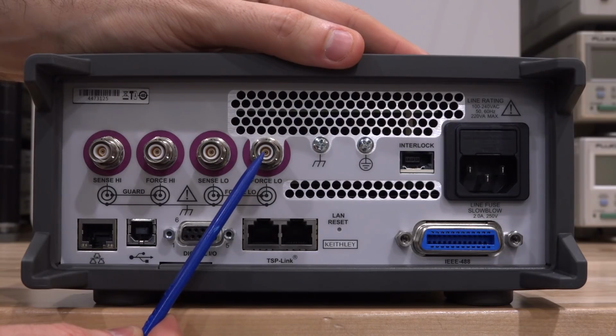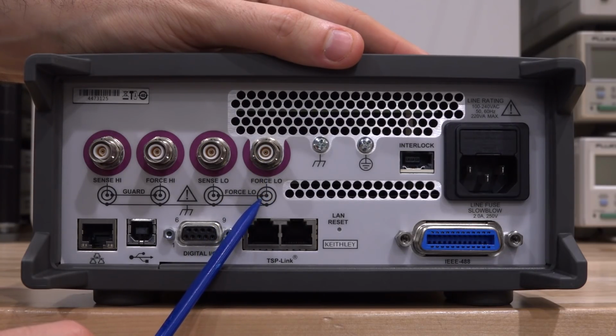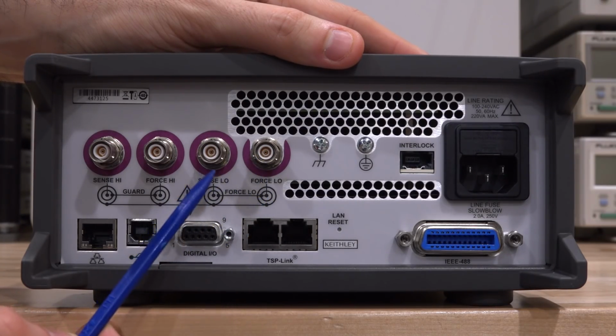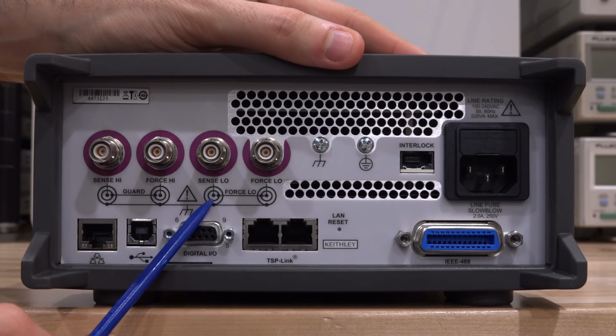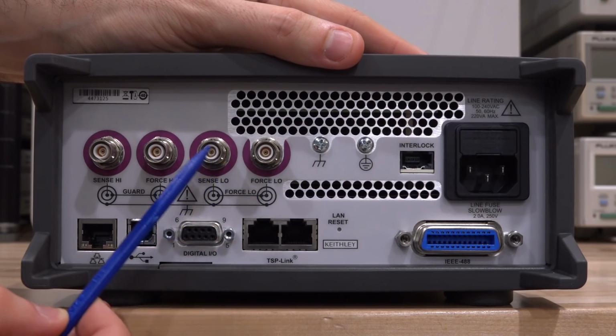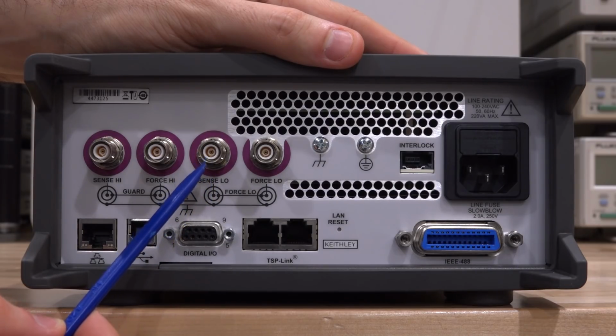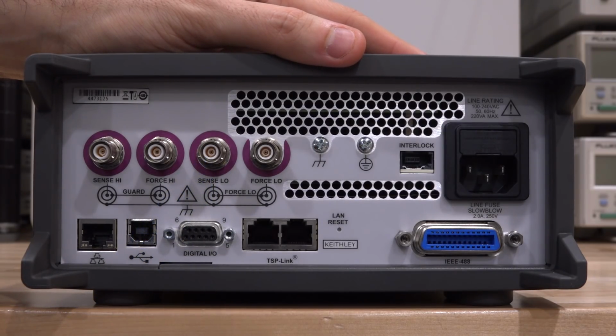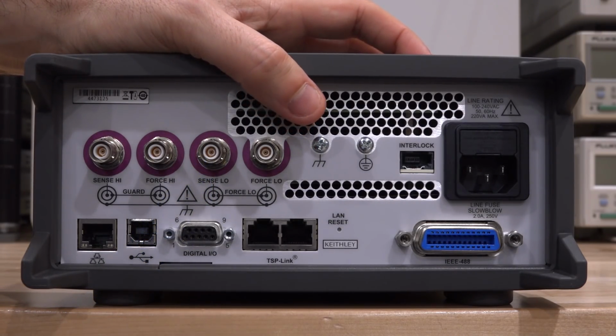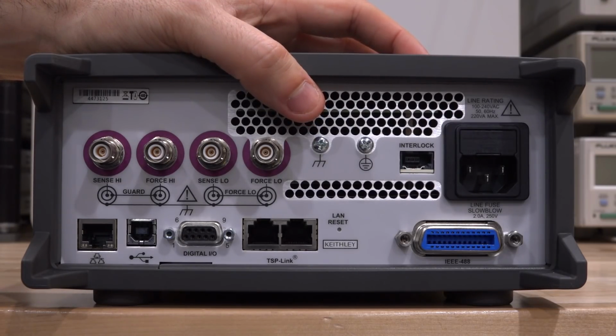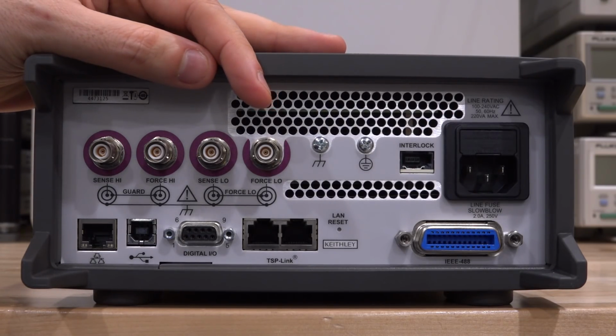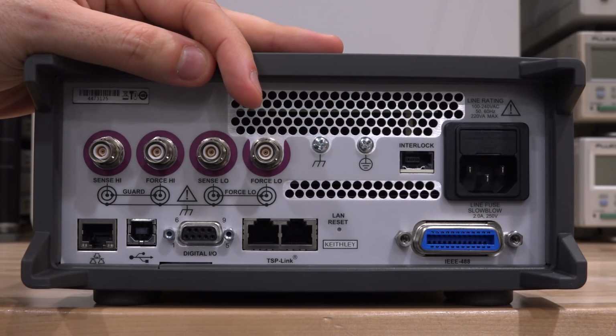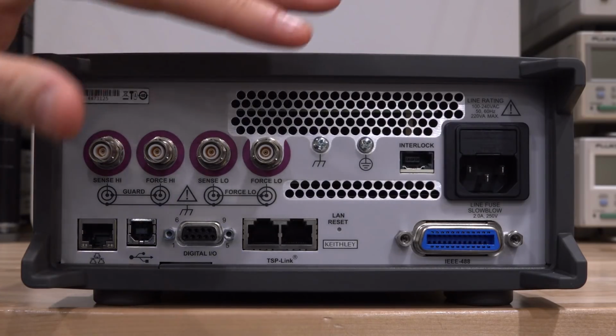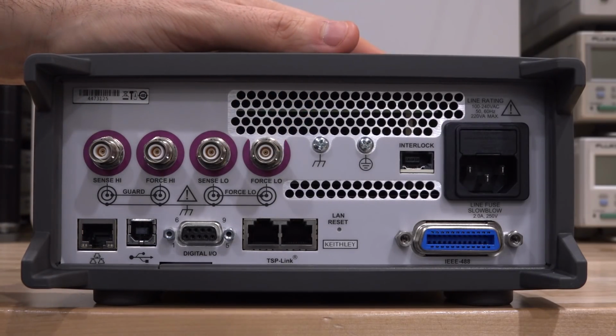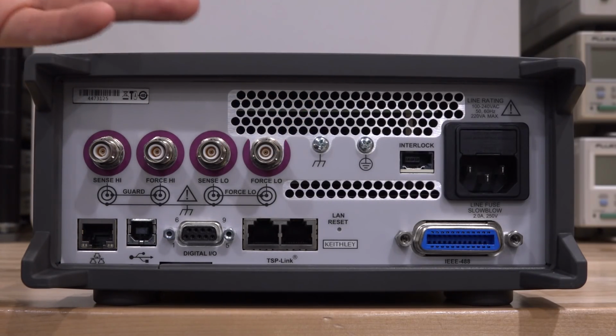So if you look at the force connector, the inner conductor and the second conductor are connected to each other, but on the sense connector, the middle conductor is connected to the force and the inner conductor is your sense. This means the sense port is shrouded, covered with the same potential as the force, allowing the reduction of leakage between those two ports. So you can still measure currents in the picoamps, hundreds of picoamps, and not have to worry about the leakage, when you're running at 1000 volts. This is crucial, and without it, you simply won't be able to do that. You can see it's really well thought out.